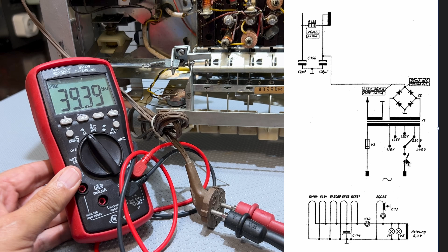With the switch closed, I'm getting what looks like an open circuit, which is not good. So I can go one step further and test different sections of this. This does not mean the transformer is bad. It does not mean that at all, and I'll tell you why.